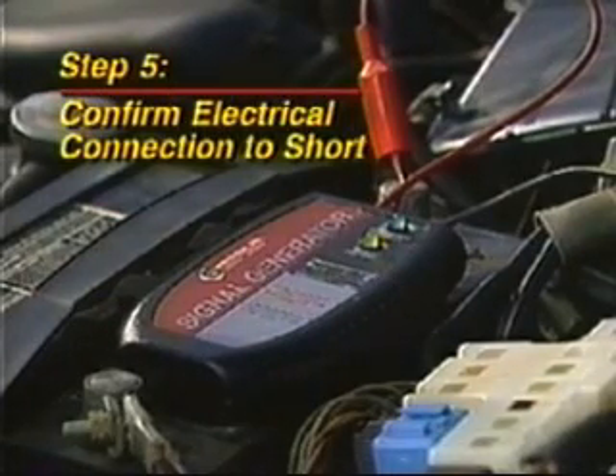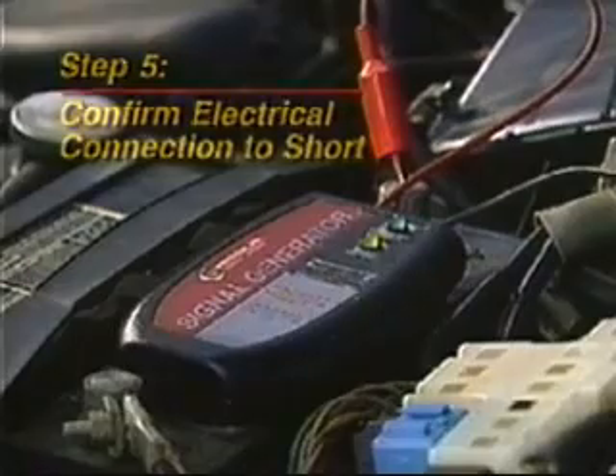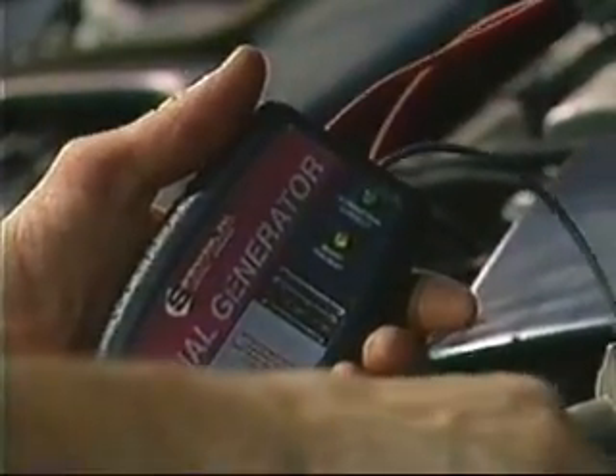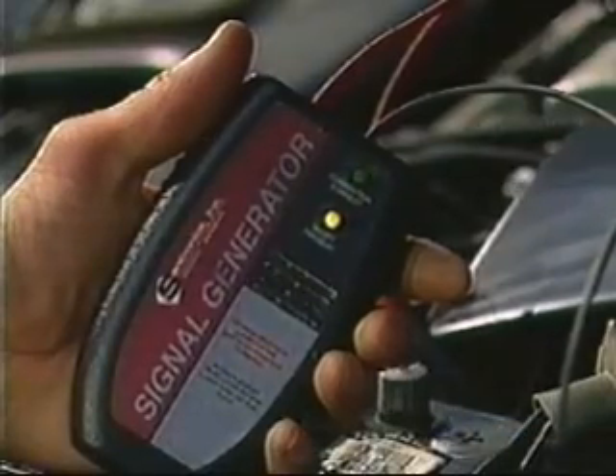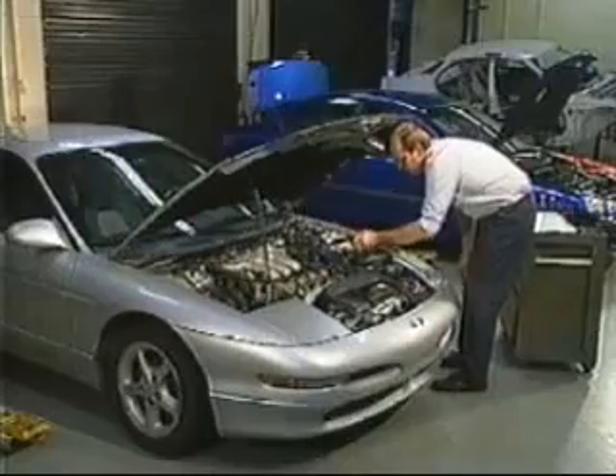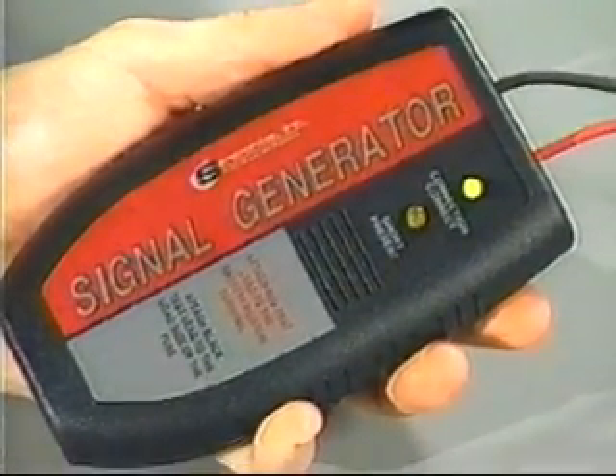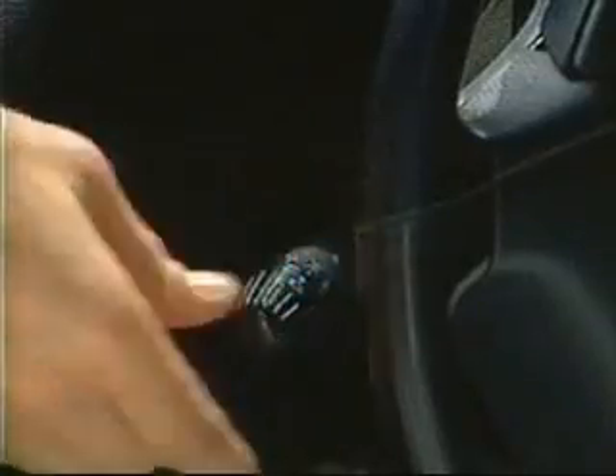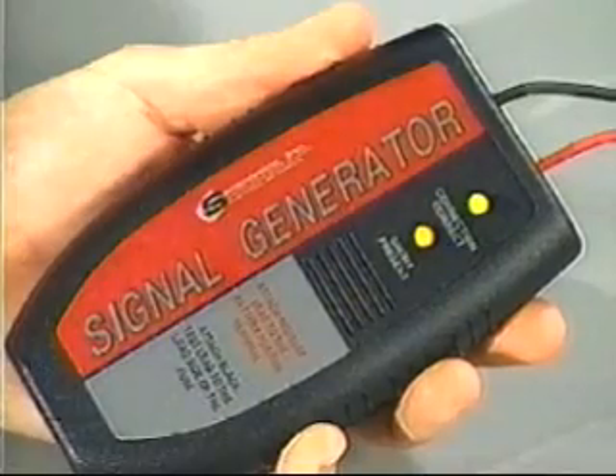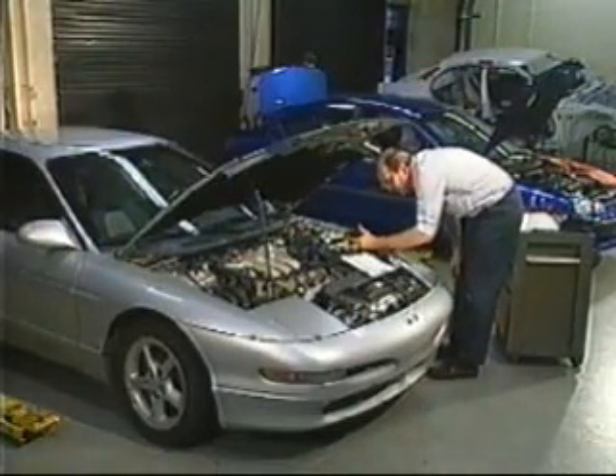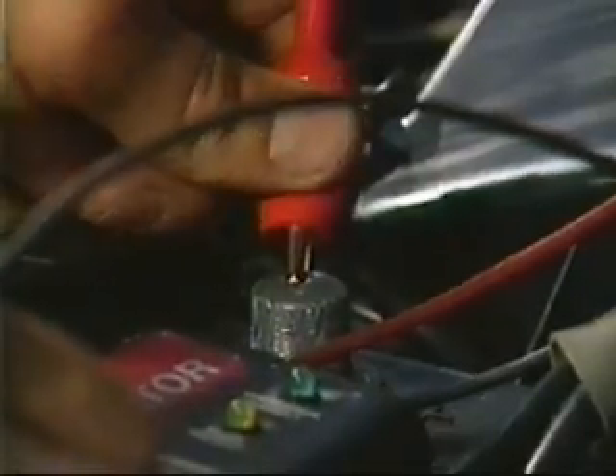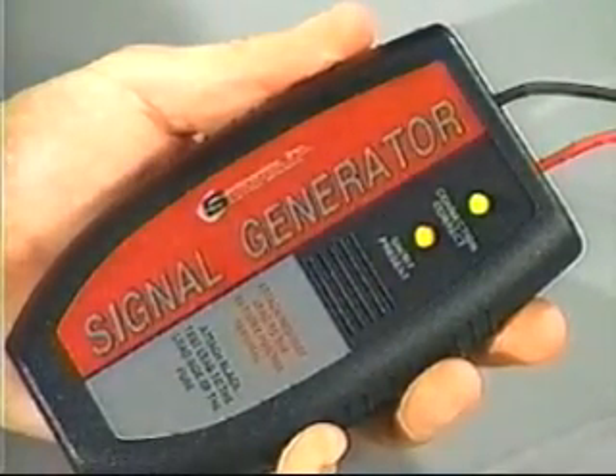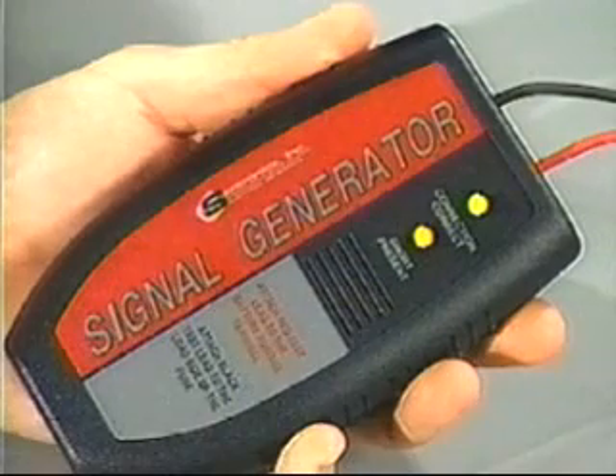Step five is to confirm that the signal generator is electrically connected to the short. Because you have already recreated the short, both the green and yellow lights on the signal generator will be lit, and you can proceed to the next step. If only the green light is lit, the signal generator is properly connected, but no short is present. Recreate the short again by operating the switches on the circuit until the yellow light is lit. If no lights are lit, the signal generator is not properly connected. Check the connection of both leads. You should proceed to the next step only when both the green and yellow lights on the signal generator are lit, indicating that the short is continually present and the signal generator is electrically connected to the short.